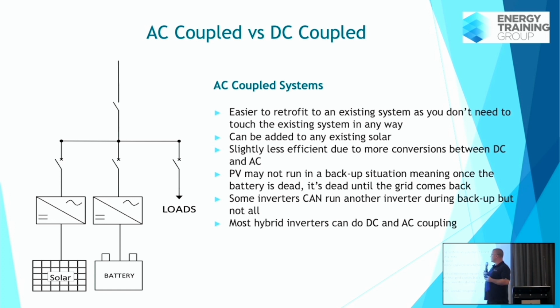An AC coupled system is probably the easiest thing to retrofit to an existing solar system. If a customer has existing solar and I don't want to touch it - we all know in solar we've got a different regs book every 3.5 minutes - so I don't want to touch the old solar system, because as soon as I do, I've got to bring it up to current standards. So I want to stay as clear from that system as I can.